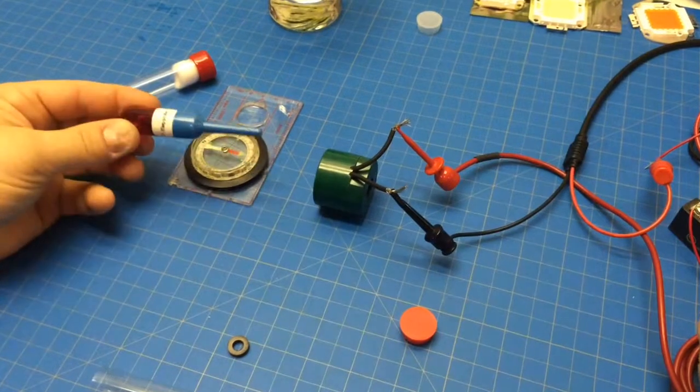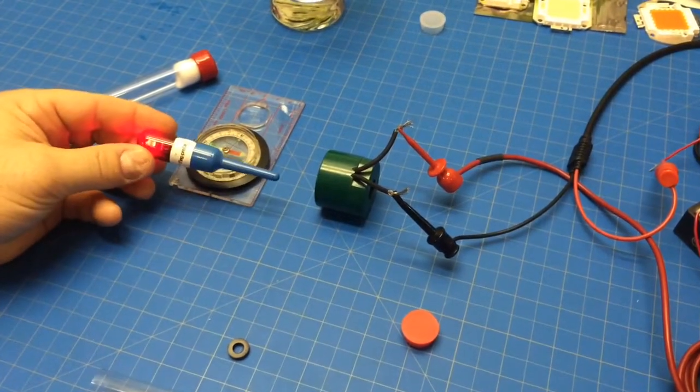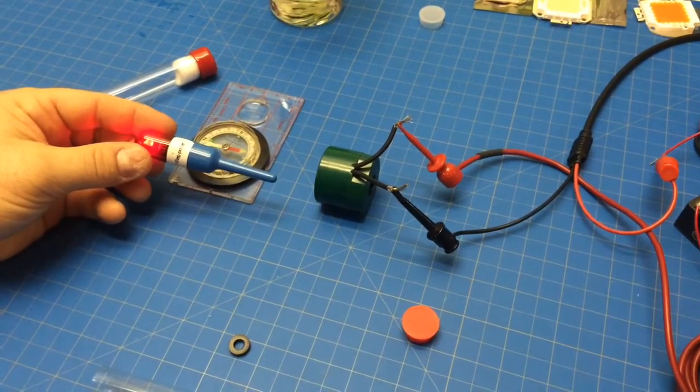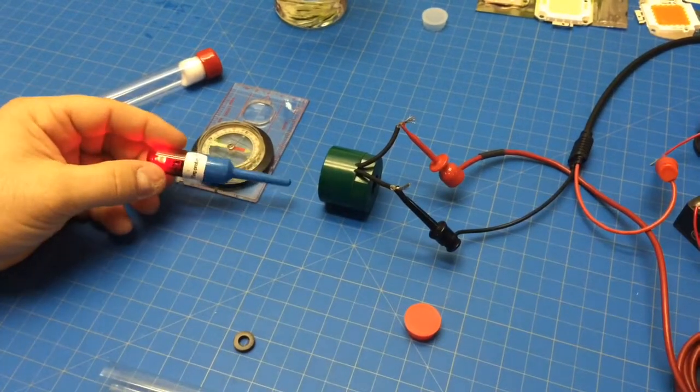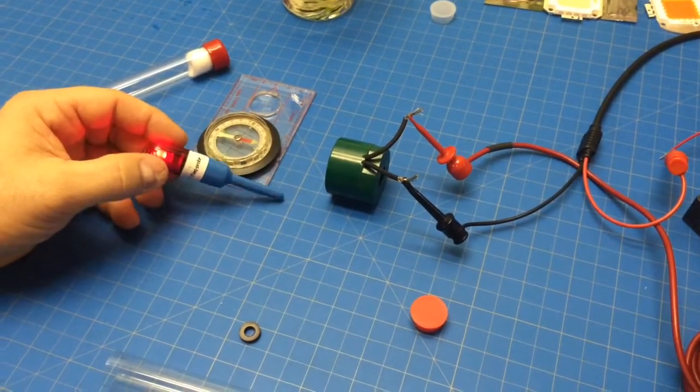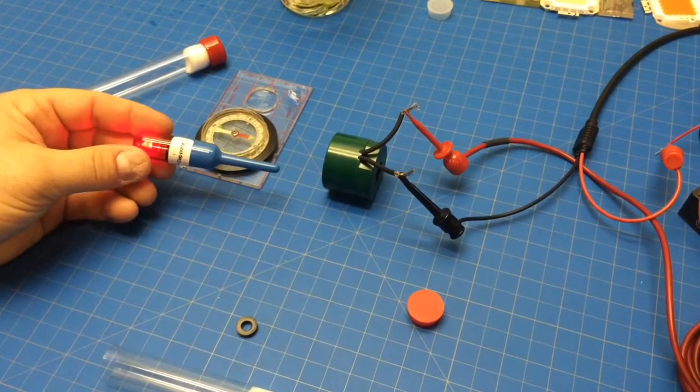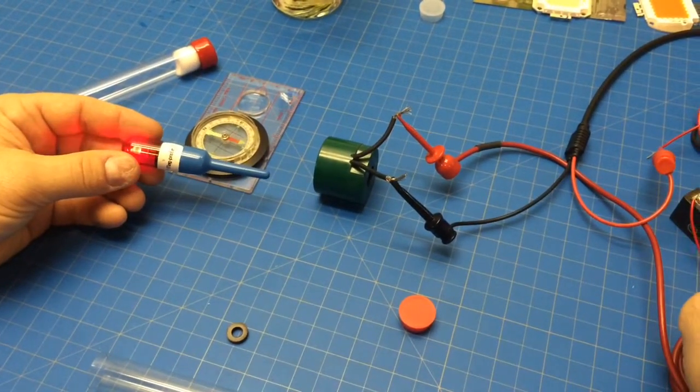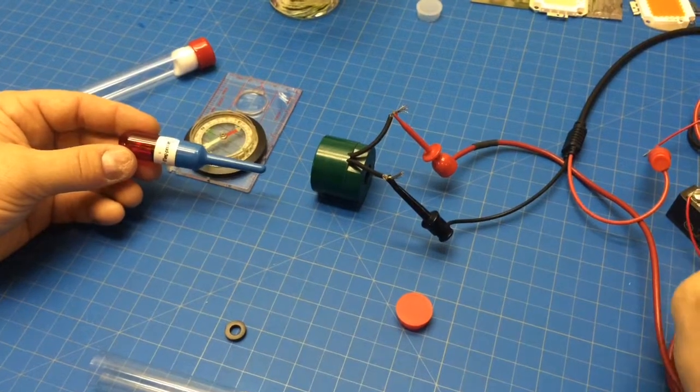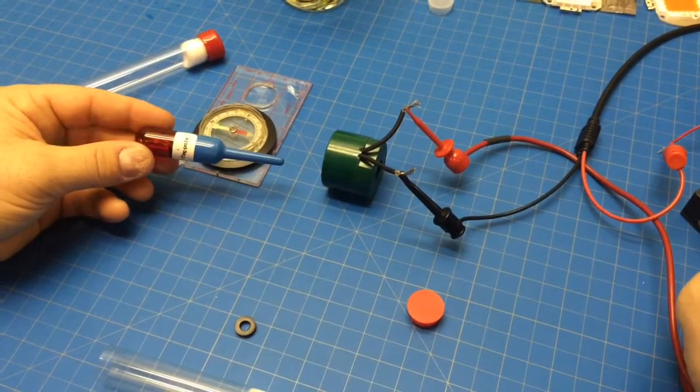And that's just helpful if you've got an elevator with 100 relays or a lot of coils. It's just really helpful. The old standby trick is to put a screwdriver next to it, but when you have a lot of relays you can't really do that trick. And certain coils that doesn't work as well and this mag probe comes in handy.